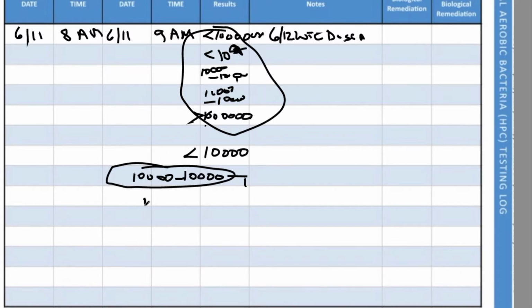If you go over a million, that is a bit more of a problem. If your reading is over a million, you basically have to do a more elaborate disinfection of the cooling tower than just an extra dose. Talk to your water treatment company or consultant about that, and they'll guide you on what you need to do. Now, before you see a million and get worried, don't panic.